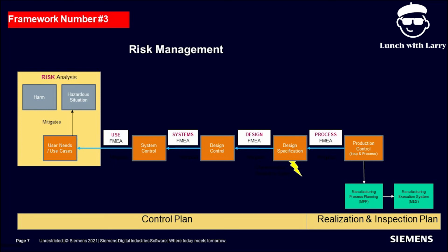If you look at this entire thing, not only do we have a control plan for the design, but we also have a control plan and an inspection plan for production. This is our entire causal chain of how a hazardous situation could possibly occur with our design, including the use of the design, meaning labeling and training, the system controls, the design controls, specifications, and production controls out through the manufacturing process. When we're finished with those production controls, we would include them in the manufacturing process planning, which would get them into the bill of process, and the bill of process would then be shared to the manufacturing execution system. So we have a total closed loop on everything required to make sure that this device is safe. Now you can imagine that if we had a failure in the field, that problem would come back into the risk management, and each one of these FMEAs would have occurrences associated with them.